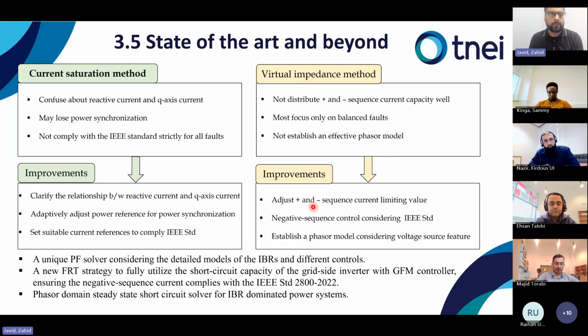These are the main contributions where we go beyond the state of the art. In the current saturation method, there was confusion about reactive current and d-q axis current, and we have cleared that. We have clarified that relationship and considered it in our methodology as well. The existing method may lose power synchronization and didn't comply strictly with the standard. I will show the results later on.